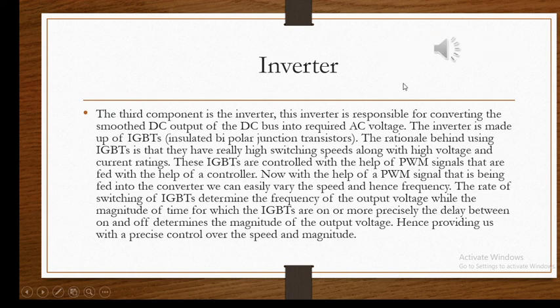The third component is the inverter. This inverter is responsible for converting the smooth DC output of the DC bus into the required AC voltage. The inverter is made up of IGBTs, which are insulated gate bipolar transistors. The rationale behind using IGBTs is that they have really high switching speeds along with high voltage and current ratings.